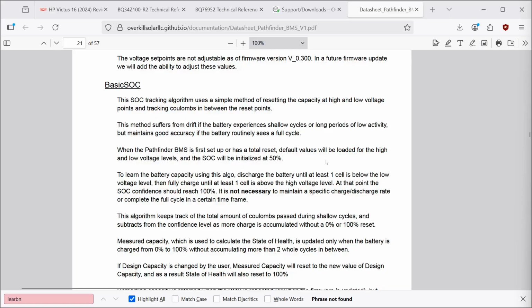When the BMS is first set up or has a total reset, the state of charge is initialized at 50%. To learn the capacity, discharge the battery until at least one cell is below the low voltage threshold, then fully charge until one cell is above the high voltage threshold.